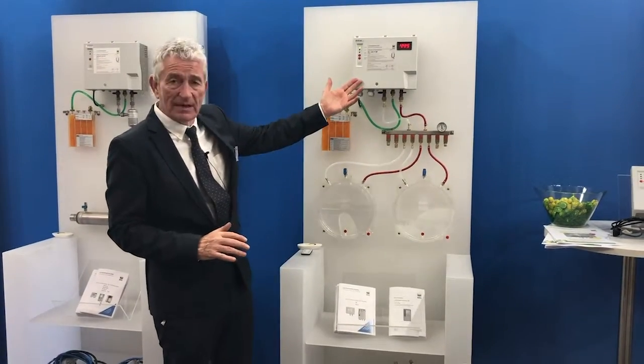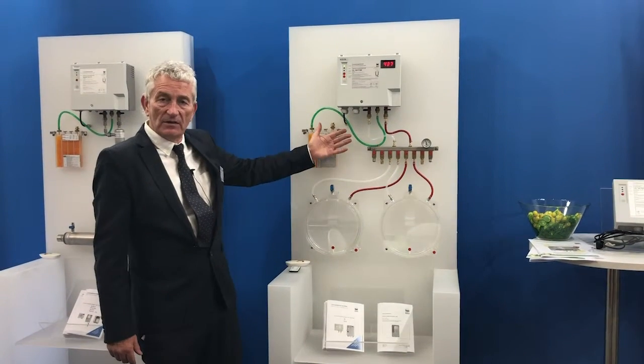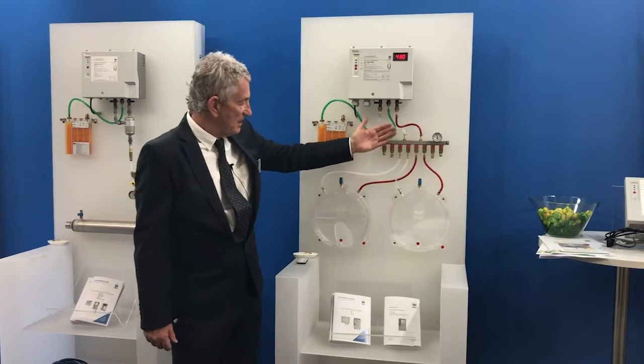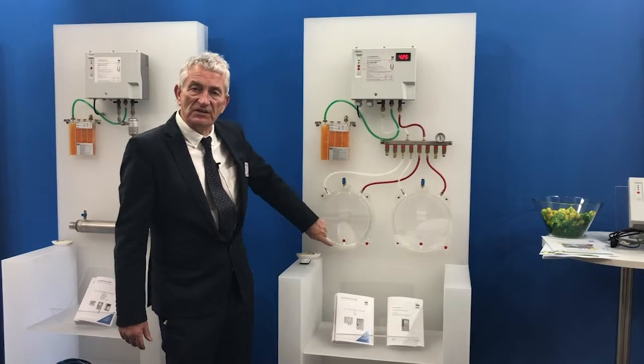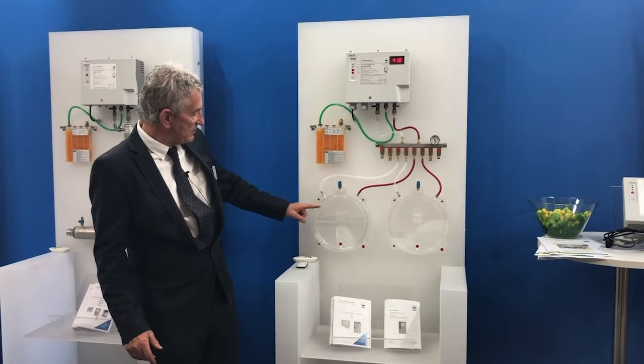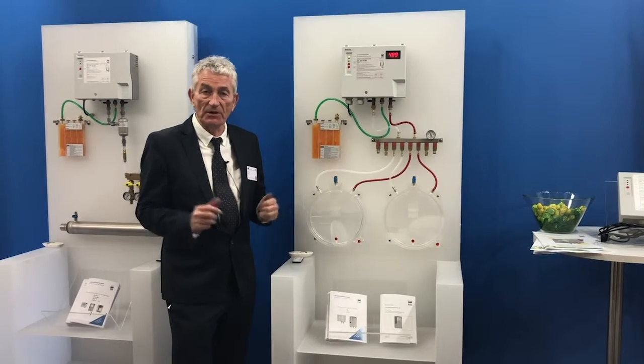And now, having been given a demonstration, I'm just going to pass that on to you very quickly. So you have here, obviously, two tanks. This is simulating the system as it is in real life. The silicon gel here — the air is passed through the silicon gel. So as it comes down into the interstitial space, there's no condensation in here because the silicon gel obviously prevents that from happening. So in the interstitial space, there are two skins — one, two. The interstitial space is the gap between the tank and the outside skin. This is the thing that is being monitored through pressure.